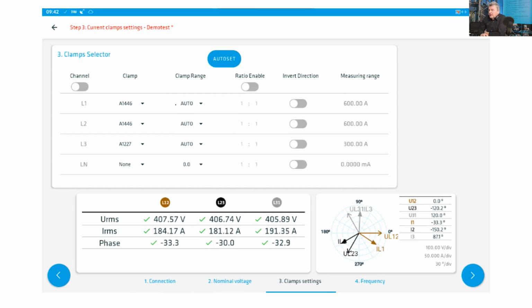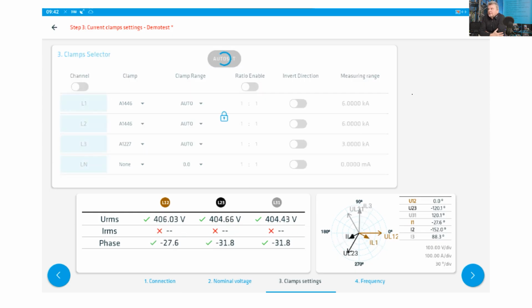We can see that two clamps are set up to 600 amps, but the third only to 300, because it is a different type of clamp and the current is okay for 300 amps. We also have an auto set button. When we start it, it will automatically start setting the optimal clamp range. The instrument starts with the highest range of the current clamps. It has already changed to the next one, and now it's analyzing whether the selected range is optimum for the active current.